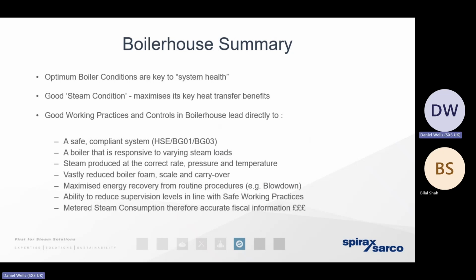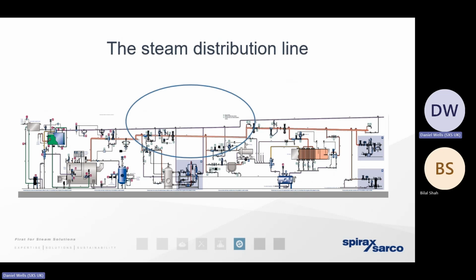And because the boiler industry is very, very competitive, unless a design engineer understands the basics of boiler controls, it's highly likely that that boiler manufacturer is going to offer a boiler that operates on the cheapest is best principle. And the client could then encounter a significant burden of maintenance or a high cost of steam and also significant carbon emissions. The good news is, if we've calculated the cost of steam, we can guarantee what the benefit is to the client by upgrading those boiler controls in many instances.